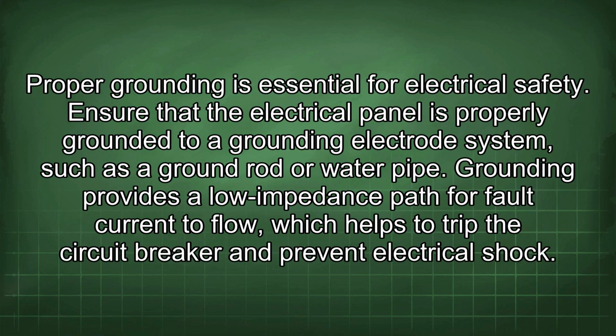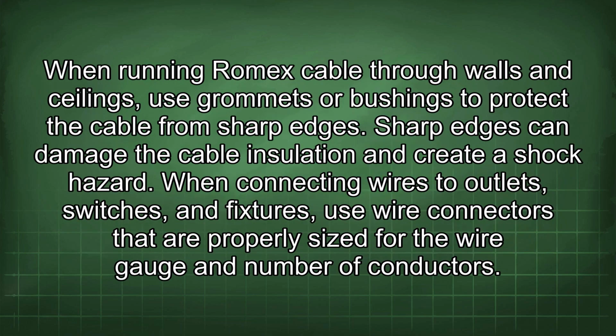Proper grounding is essential for electrical safety. Ensure that the electrical panel is properly grounded to a grounding electrode system, such as a ground rod or water pipe. Grounding provides a low impedance path for fault current flow, which helps to trip the circuit breaker and prevent electrical shock. When running Romex cable through walls and ceilings, use grommets or bushings to protect the cable from sharp edges. Sharp edges can damage the cable insulation and create a shock hazard.